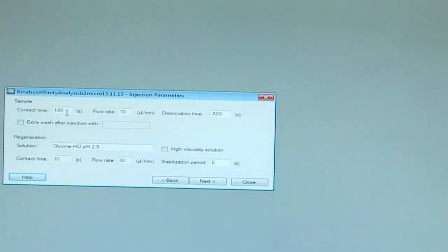The sample contact time of 180 seconds is selected. Flow rate of 30 microliter per minute is selected. Dissociation time of 600 seconds is selected. Coming to the regeneration solution is glycine HCl pH 2.5 with a contact time of 30 seconds, a flow rate of 30 microliter per minute, stabilization time of 0 seconds.